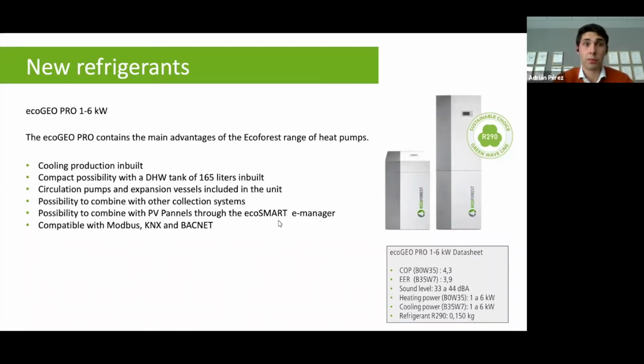It includes the possibility of cooling, and of compact units with a domestic hot water tank. As a default, the circulation pumps for brine and production are included, as well as the expansion vessels. We can combine it with our air units, with the EcoSmart eManager, and also with Modbus, KNX, or BACnet. This unit only includes 150 grams of refrigerant inside, so it's the only product like this nowadays in the market.